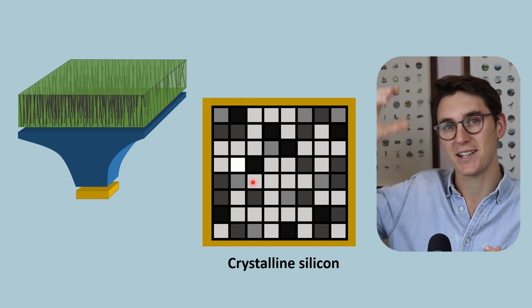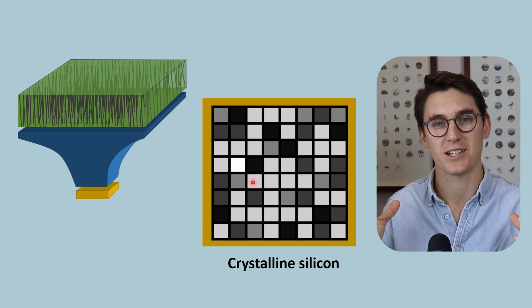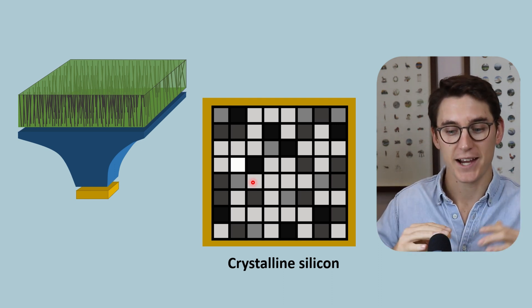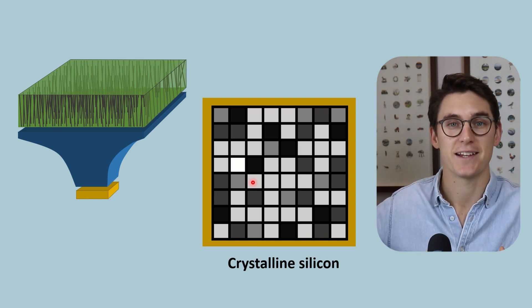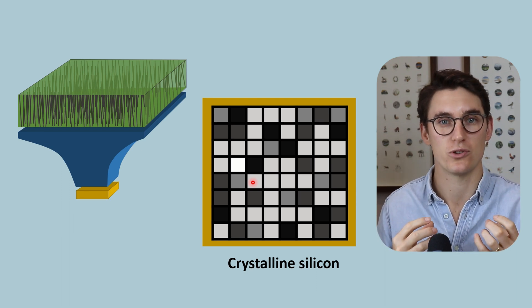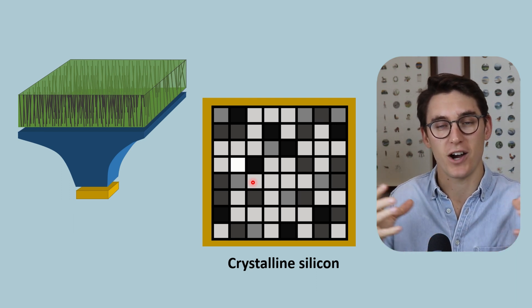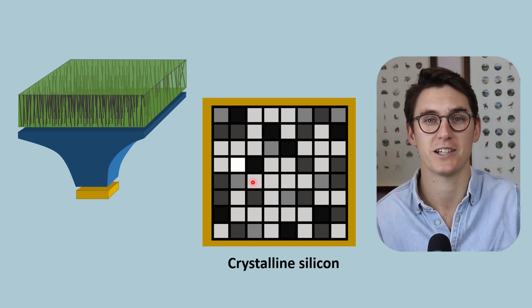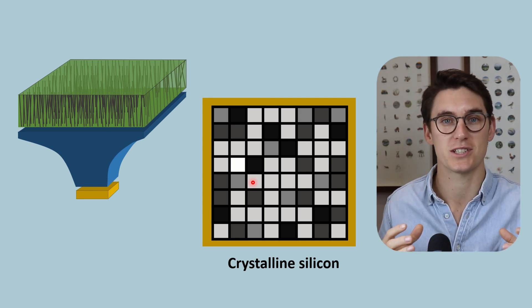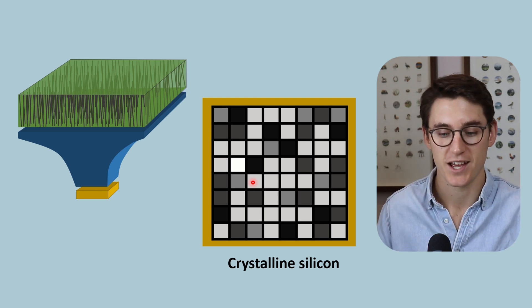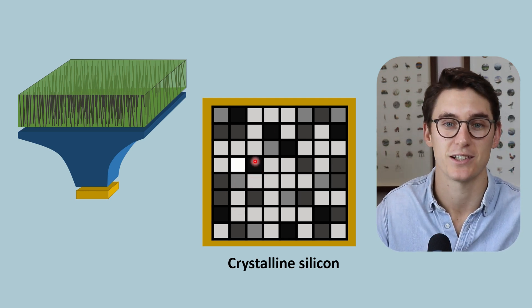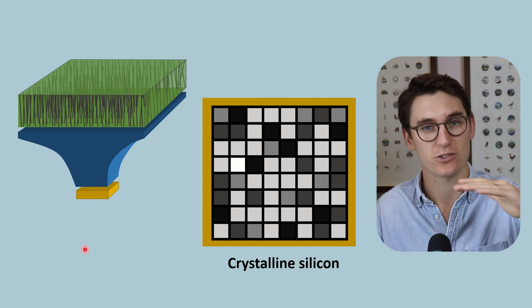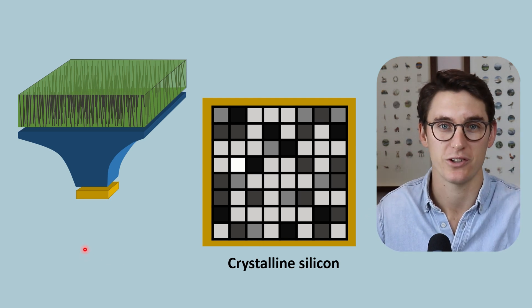So what we've done here is we've taken X-ray energy, converted it to light, channeled that light down onto our CCD chip, the light hits that crystalline silicon and electrons are released in proportion to those lights. Those electrons are housed within a specific dexel that corresponds to a specific pixel in our image and those dexels are prevented from merging together by these voltage gates that are etched onto this crystalline silicon of our CCD chip. We read out those dexels sequentially and create our radiograph.